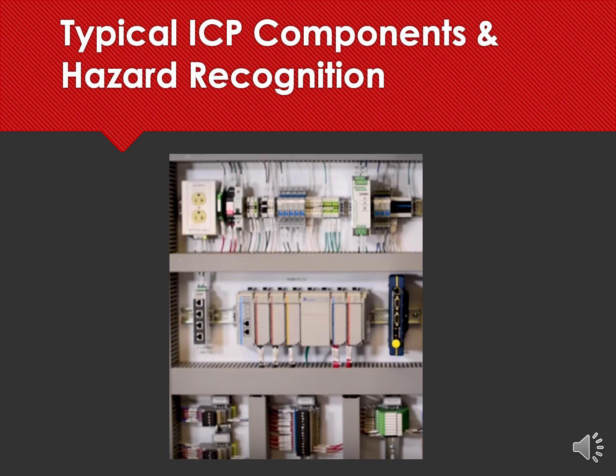But as you see the way the overview of the panel is depicted in front of you, the top tier of the cabinet is actually the incoming power circuitry. Both the AC and DC power is in that tier of the panel. The middle panel is actually the brains of the outfit. This includes a programmable logic controller and some of the Ethernet connections and radio connections in the panel. And the bottom tier is actually the terminal blocks, where all of this control power is directed to the actual equipment that it controls. So let's go to the next slide and we'll break down each one in a bit more detail.